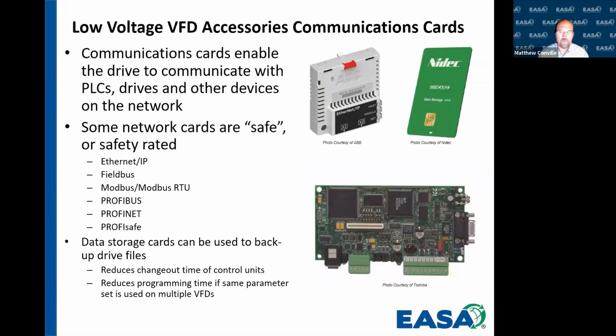Not every drive do we want to be standalone. So we need to have communication cards to be able to do that. Some drives come with communication cards and some have to be procured with it. And what this does is it gives the drive the ability to communicate with other drives on the same industrial network, with other PLCs on the network, and even with any other device that we may have, laptops, it could be tablets, smartphones, whatever has access to the industrial network. We have to be really careful because not all these communication cards are created equal.